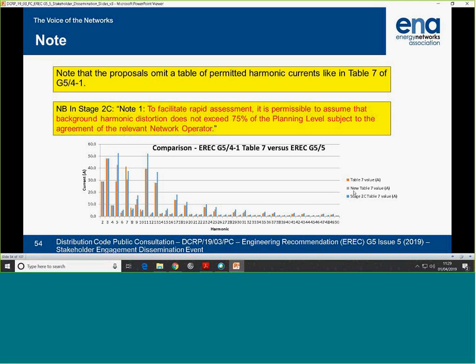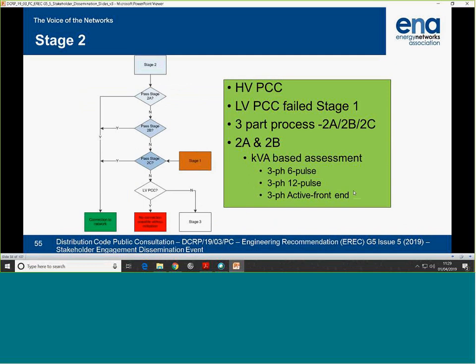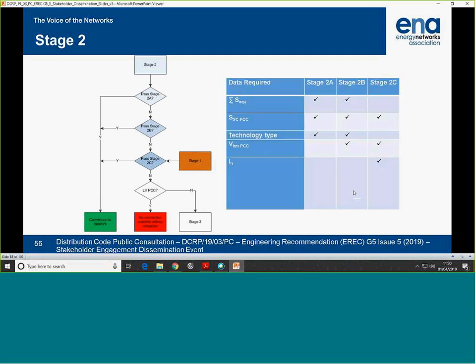Right, that gets me to stage 2. Stage 2, high voltage point of common coupling, I would describe it in the old terms. It goes up to less than 33 kV. For LV, those that failed stage 1 come in here. So stage 2 comes in because your point of common coupling is at a higher voltage. It's a 3-stage process, 2A, 2B, 2C. If we look at stage 2 inputs, the same idea applies: the information required increases as you go through the stages. In stage 2C, you've got the harmonic currents actually being used. It's actually using the emissions that are stated for the product.